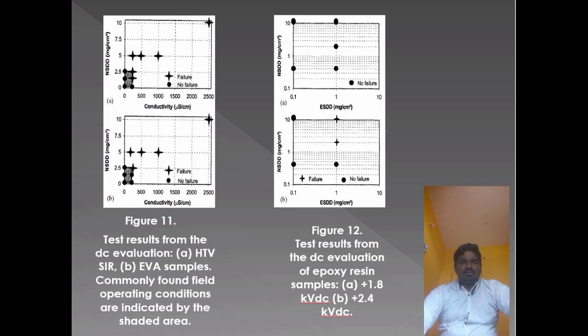Results obtained from the AC evaluation of the epoxy resin samples clearly demonstrated the outstanding electrical performance of these polymeric castings when exposed to pollution and high field stresses. No failure was observed during the AC testing program at two different test voltage levels, that is 1.8 and 2.4 kilovolts. On the other hand, the DC evaluation of these samples yielded somewhat different results. In figures 12A and 12B, the results obtained from the DC evaluation of the epoxy resin samples for the test voltage values of 1.8 and 2.4 kilovolts DC respectively are illustrated graphically.